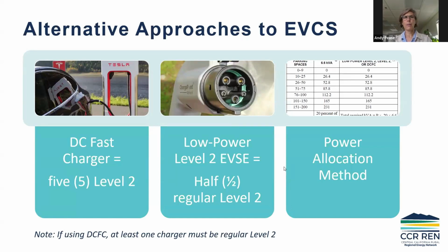There's alternative approaches. That's kind of a prescriptive using that table, but they also let you do some trade-offs. They're trying to accommodate changing technology and market. So if you have DC fast chargers, they count as 5 level 2s. So if you were required to do 10 level 2 chargers, you could take away 5 of them and put in 1 DC fast charger. Or the opposite, if you're doing a whole bunch of low power level 2s, then you would need twice as many.